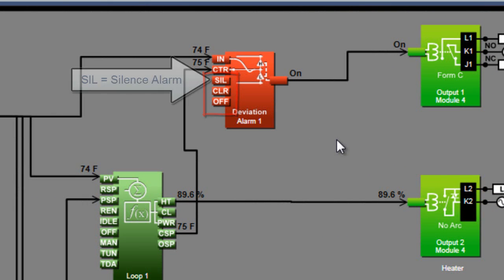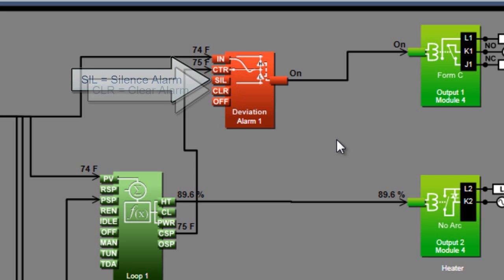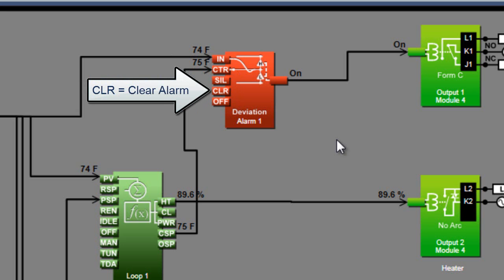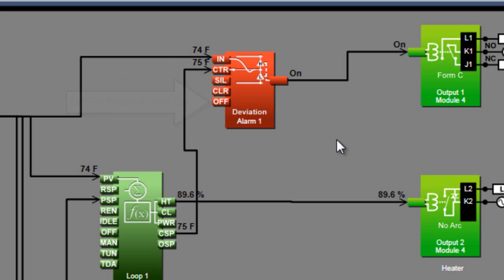You may have noticed that there are three receivers on the block that I haven't used. The SIL receiver attempts to silence the alarm when it receives an on signal. The CLR receiver attempts to clear the alarm when it receives an on signal. And the off receiver overrides the alarm when it receives an on signal.